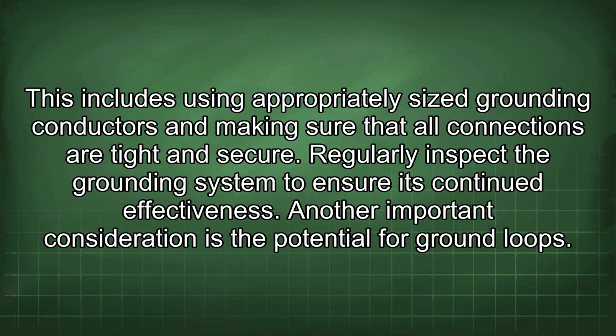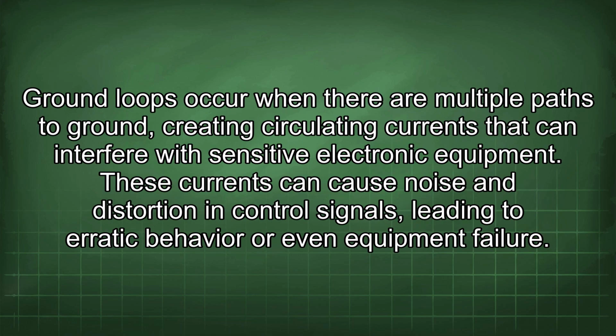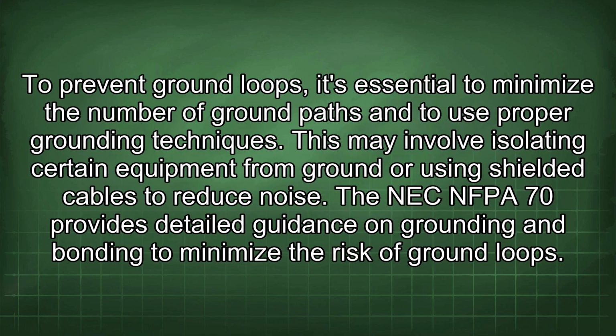Another important consideration is the potential for ground loops. Ground loops occur when there are multiple paths to ground, creating circulating currents that can interfere with sensitive electronic equipment. These currents can cause noise and distortion in control signals, leading to erratic behavior or even equipment failure. To prevent ground loops, it's essential to minimize the number of ground paths and to use proper grounding techniques. This may involve isolating certain equipment from ground or using shielded cables to reduce noise. The NEC NFPA 70 provides detailed guidance on grounding and bonding to minimize the risk of ground loops.